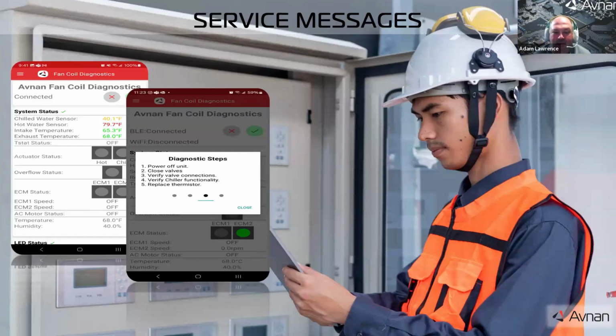Designing these service messages is part of the firmware development. It ties back to the unified fault taxonomy. Each fault code has an associated message or troubleshooting tip. Best practice is to work with your tech support and field engineer teams to craft those messages so they're as helpful as possible. Think of it as embedding a troubleshooting guide into the unit.